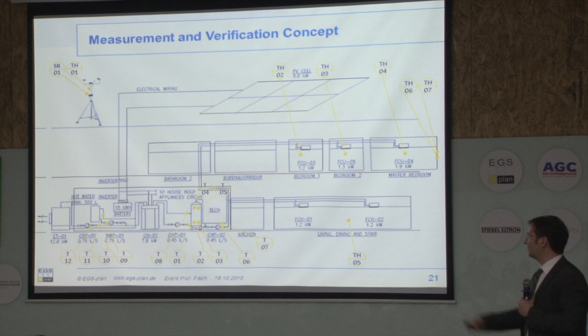We have electric meters integrated in the PV system, in the battery, and also measuring how much energy comes from the public grid. We have meters to measure the electric input into the chiller and the cooling energy output, so we can calculate the performance of the chiller, because that's quite crucial.